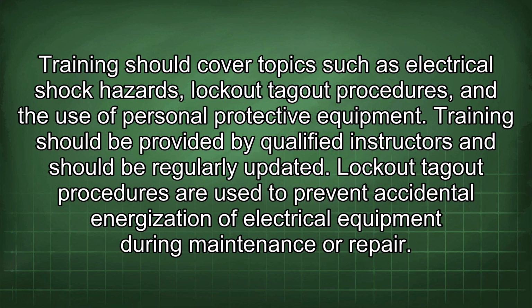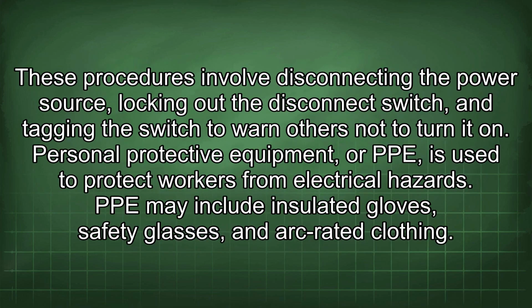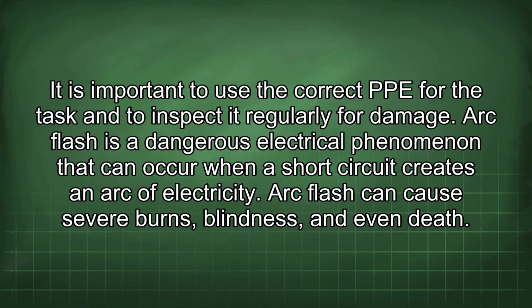Lockout-tagout procedures are used to prevent accidental energization of electrical equipment during maintenance or repair. These procedures involve disconnecting the power source, locking out the disconnect switch, and tagging the switch to warn others not to turn it on. Personal protective equipment (PPE) is used to protect workers from electrical hazards. PPE may include insulated gloves, safety glasses, and arc-rated clothing. It is important to use the correct PPE for the task and to inspect it regularly for damage.